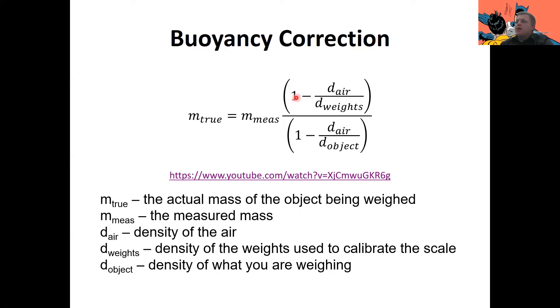So on top of this ratio, we have one minus the density of air, which I'll provide for you in the labs, divided by the density of weights. So in the analytical balances we use in this class, the density of our weights is always 8.0 grams per mil. And this is that internal calibration weight inside of our balance. And then on the bottom of this, we have one minus the density of air again, divided by the density of our objects. So this is the density of our sample. So if we're trying to measure the mass of water, this would be the density of water. We're trying to measure the mass of a block of lead. This would be the density of lead.